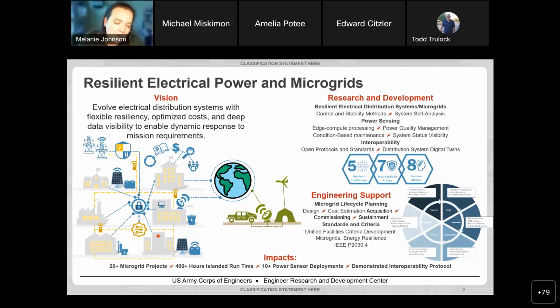We power system geeks would say they are on the grid edge, but they can be put throughout a distribution system, and they help us examine power quality in the system. We can use them to some extent to perform condition-based maintenance and figure out when equipment is going to fail before it fails. And they give us a way to check the system status and create a validation channel if you think that other control systems and monitoring systems have been compromised, like from a cybersecurity standpoint.